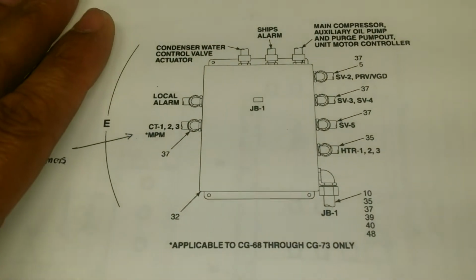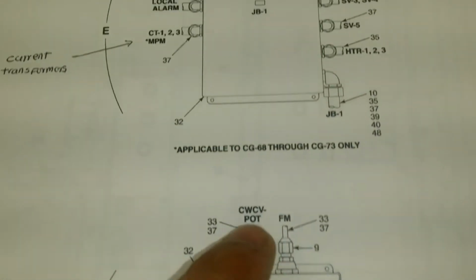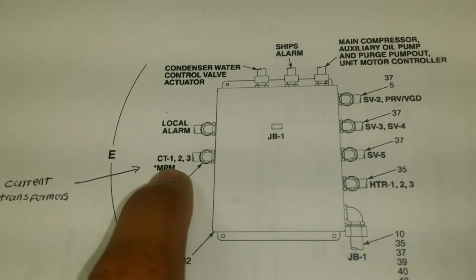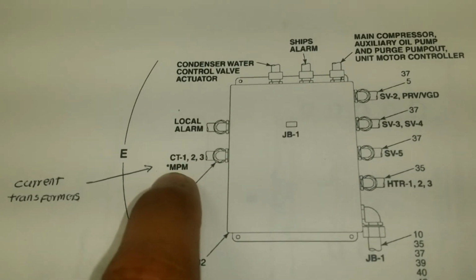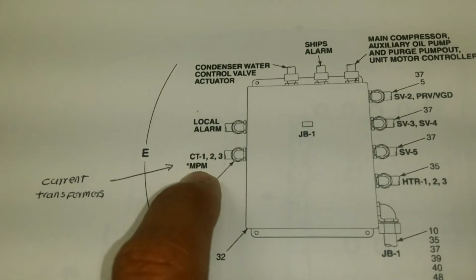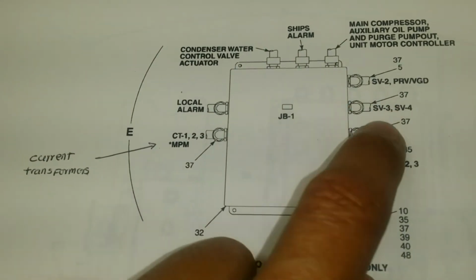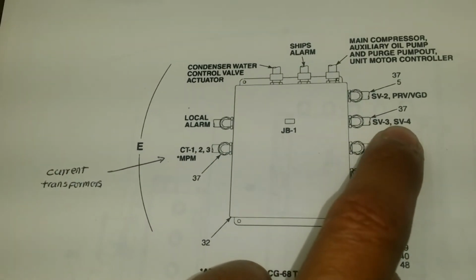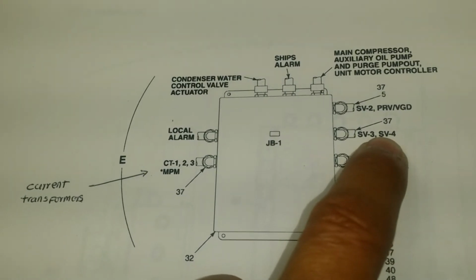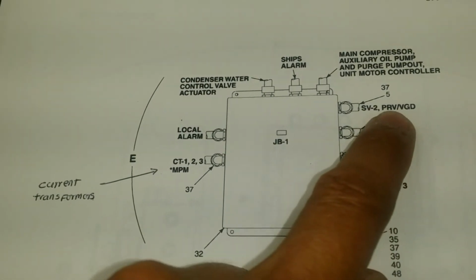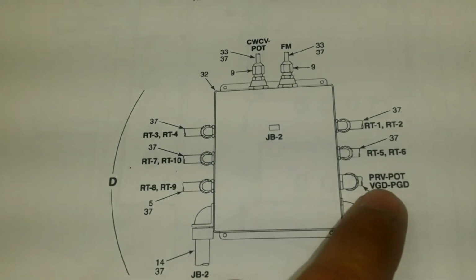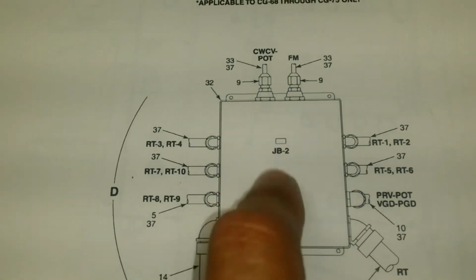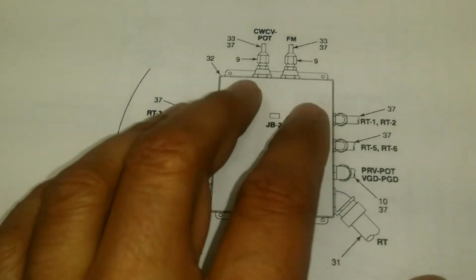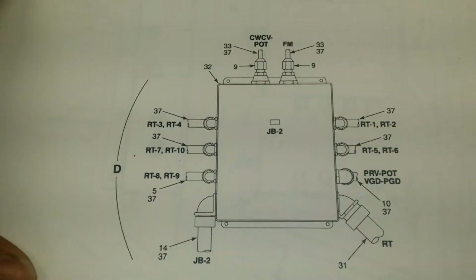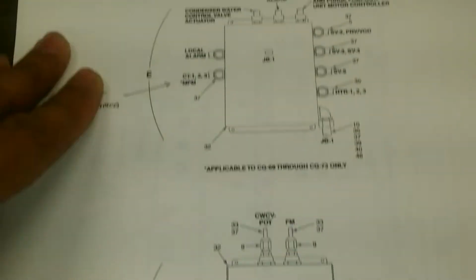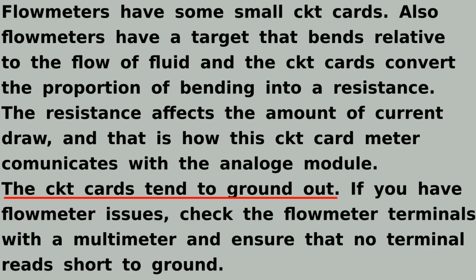Well, I came across this page over here which talks about JB1 and JB2, and it is great because it is a quick reference to let you know what is connected. Like we can see the current transformers, the motor protection module, and over here some of the SV valves. I think 3 and 4 is the hot gas bypass valve, and then obviously the PRV commands, and it looks like this one over here has the PRV sensors. Well, actually I talked about this earlier, but just make sure that if you ever need to troubleshoot and you're wondering where something is connected, you can find this page in your book.